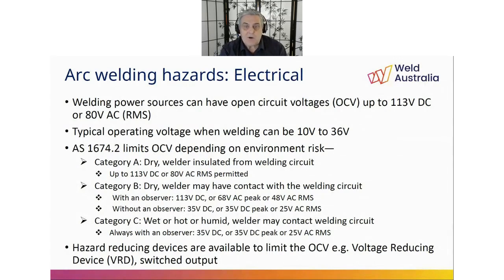Sweat and dampness rapidly compromises the insulation resistance of protective gloves and clothing. It is important to note that most electric shocks are received by welders when changing electrode or when preparing to initiate the arc, or even by their assistants whilst holding a workpiece.